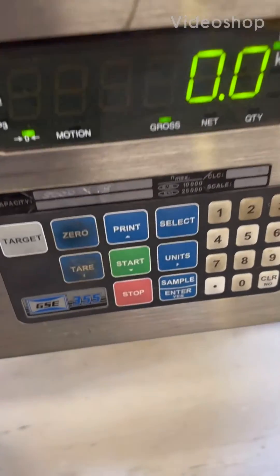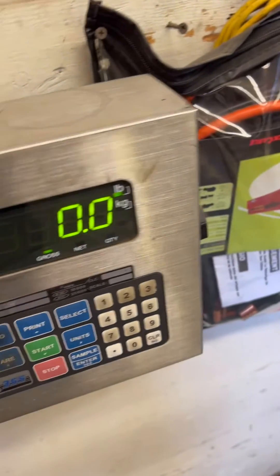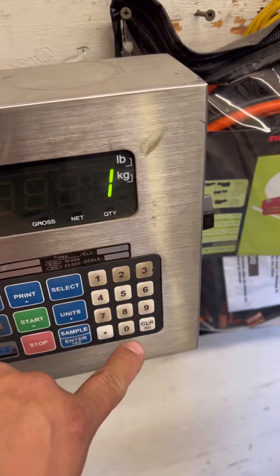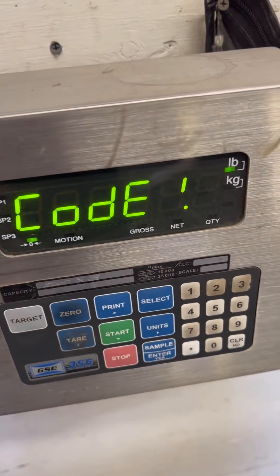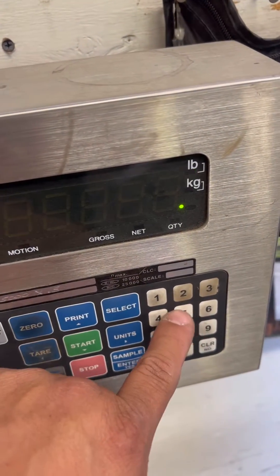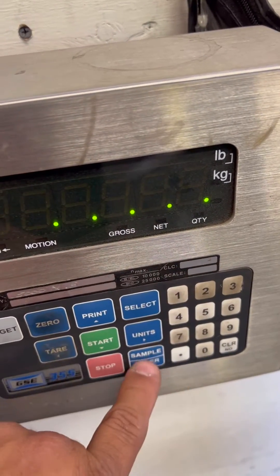This is a calibration adjustment of a GSE 355. Basically, what you're going to do is punch in 100 and select it. It asks for a code — the code is 5, 4, 3, 2, 1 — then press enter.